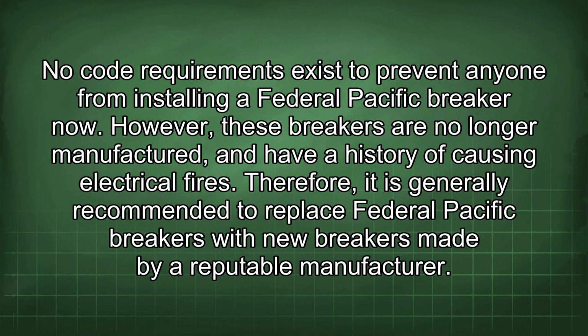No code requirements exist to prevent anyone from installing a Federal Pacific breaker now. However, these breakers are no longer manufactured and have a history of causing electrical fires. Therefore, it is generally recommended to replace Federal Pacific breakers with new breakers made by a reputable manufacturer.